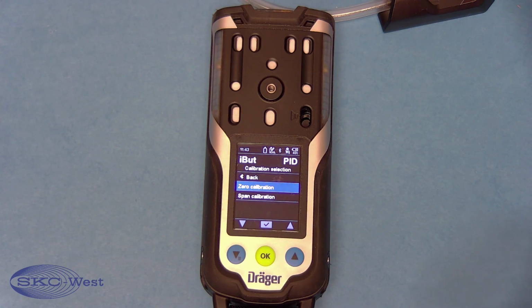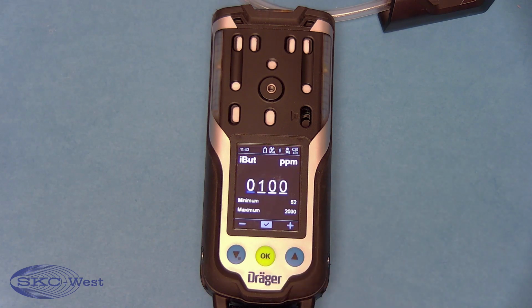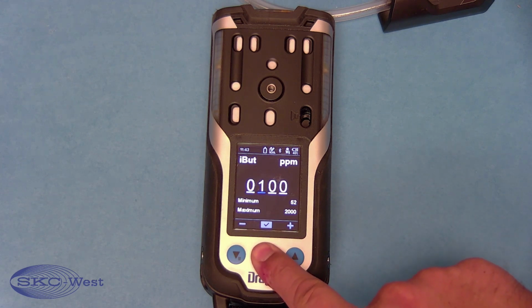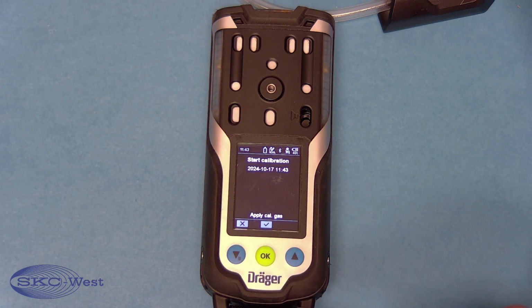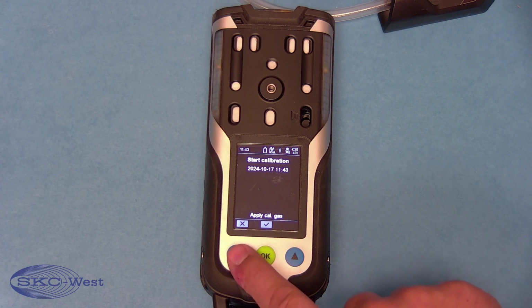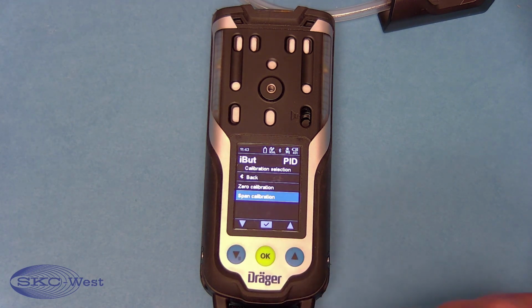You would go to span calibration, hit OK, and you could type in whatever ppm level or percent by volume level, depending on the sensor you have, so make sure you check your label of gas. You would hit OK, and then you would flow gas again. We're not going to do it right now, but that's how you do it.